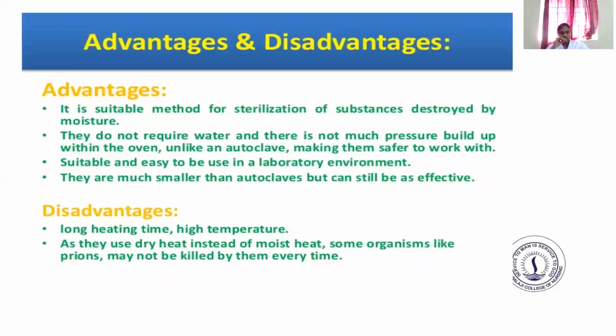Let me see the advantages and then disadvantages. First of all, we are going to see the advantages. It's very, very important. It is a suitable method of sterilization of substances destroyed by moisture. They do not require water and there is not much pressure buildup within the oven, unlike an autoclave, making them safer to work with. Suitable and easy to be used in a laboratory environment, they are much smaller than autoclaves but can still be as effective.